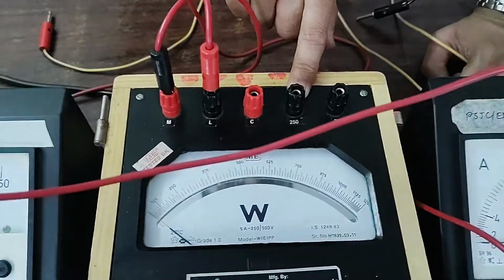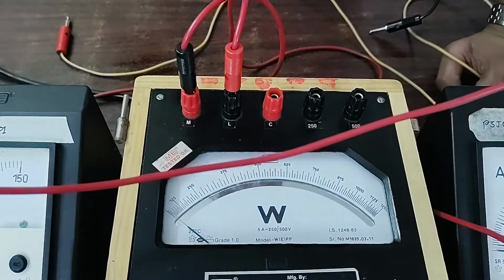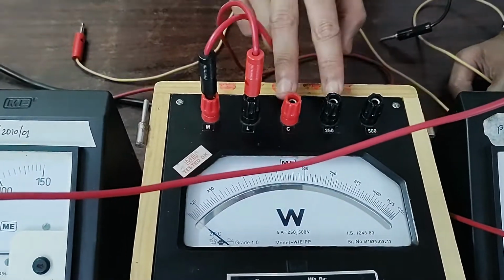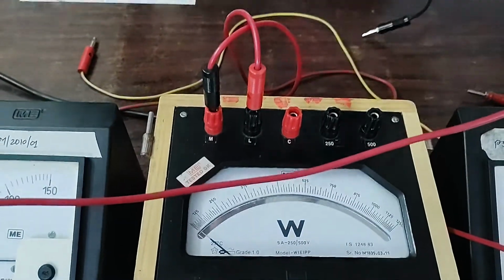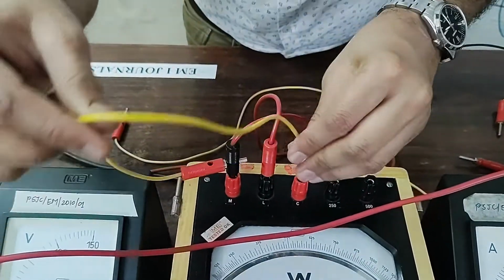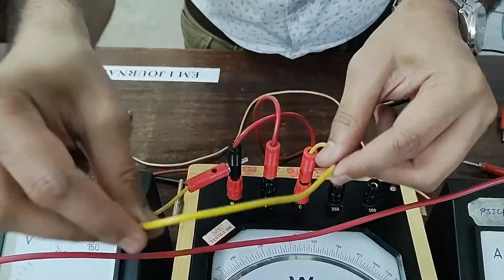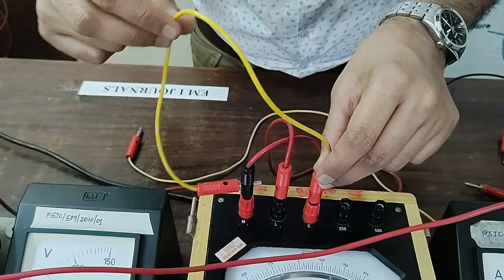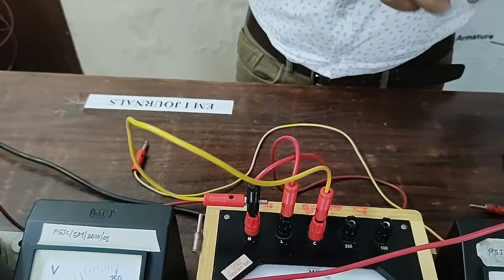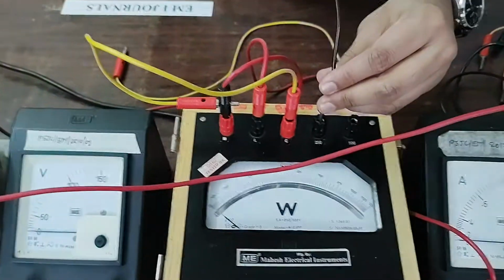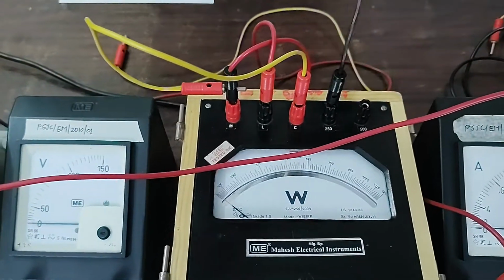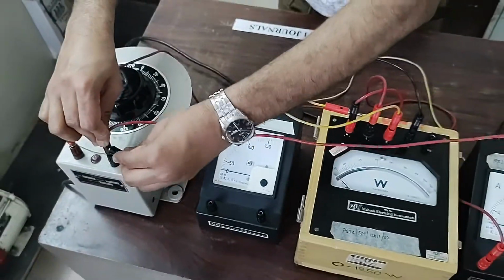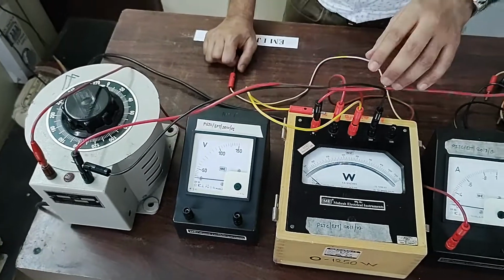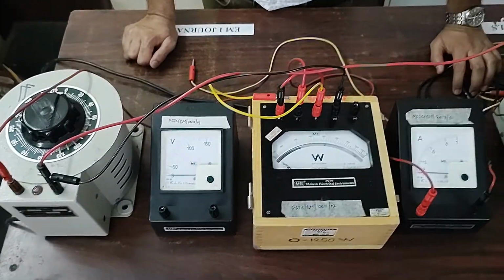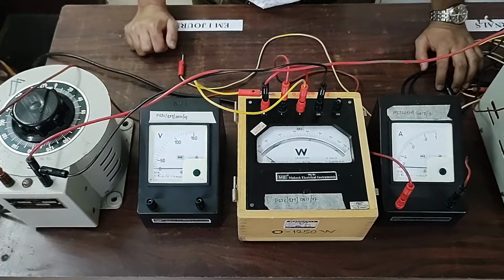And for this experiment we will be using the 250 volt voltage range. So M and C are not internally connected, but according to the circuit diagram, to bring the voltage coil in the circuit, we will have to connect a small link between M and C. So this will form the connection of the voltage coil from the mains terminal, and we will select the range of 250 volt. From here we have to take the connection to the neutral terminal of the auto transformer. From the circuit diagram we have to keep in mind that a total of 3 wires will be meeting at the neutral terminal.